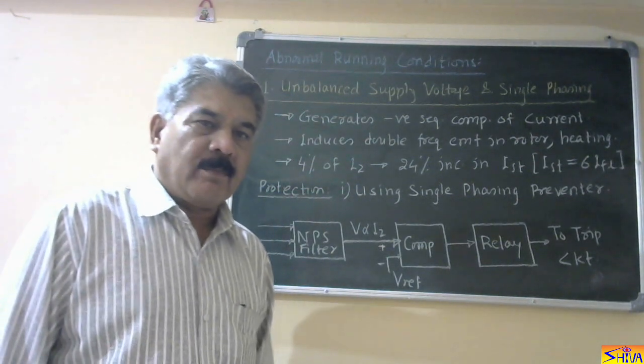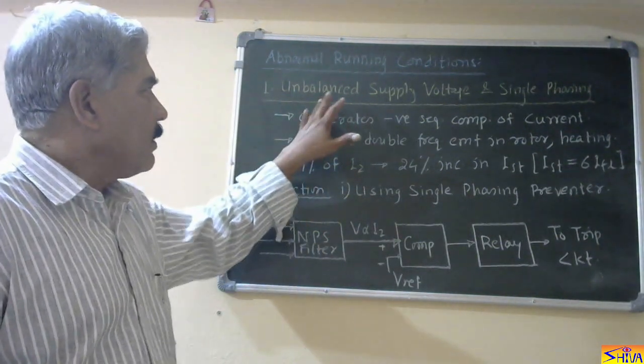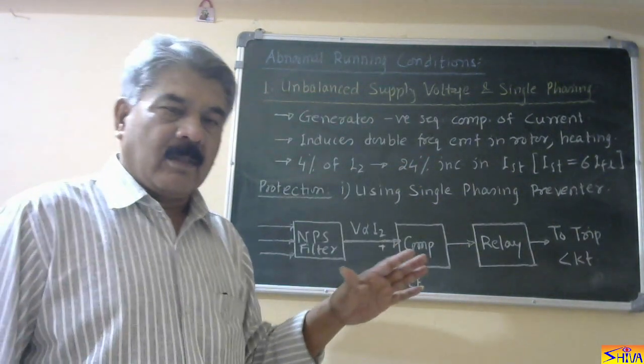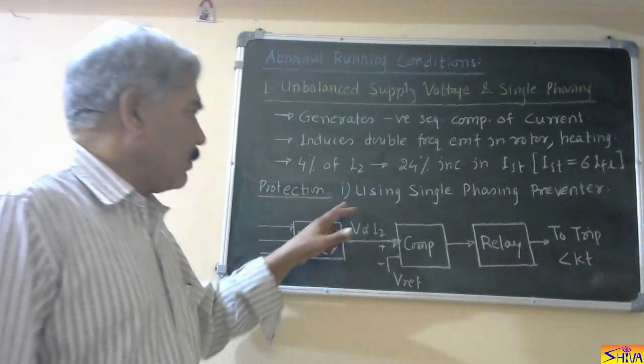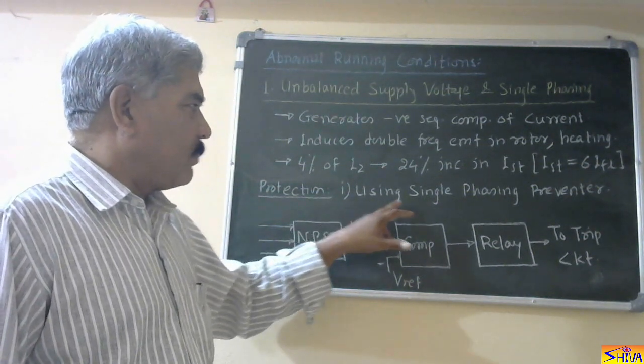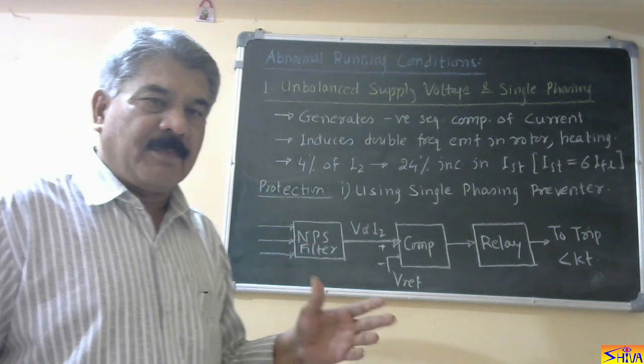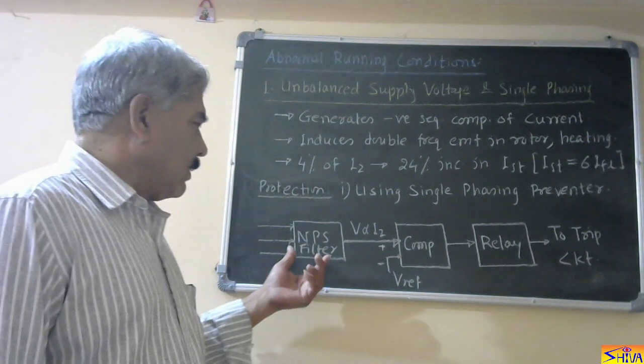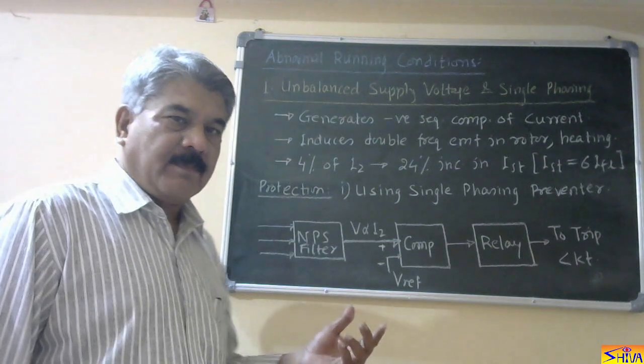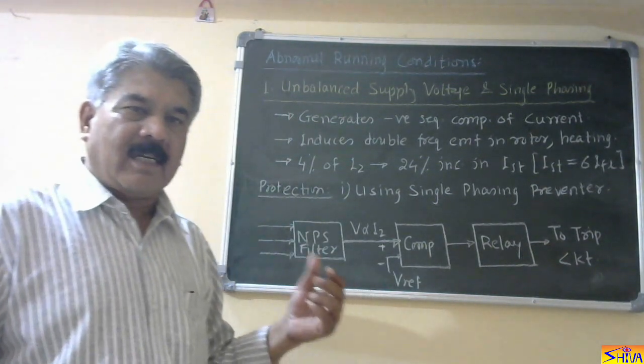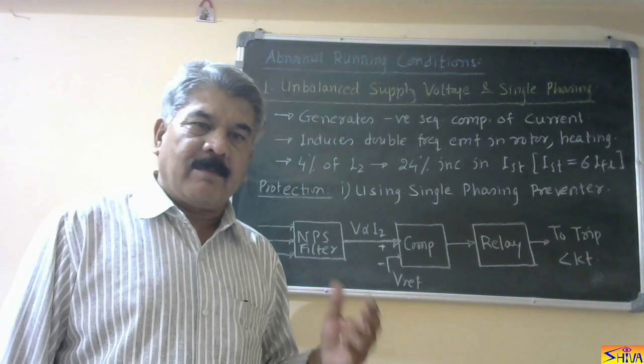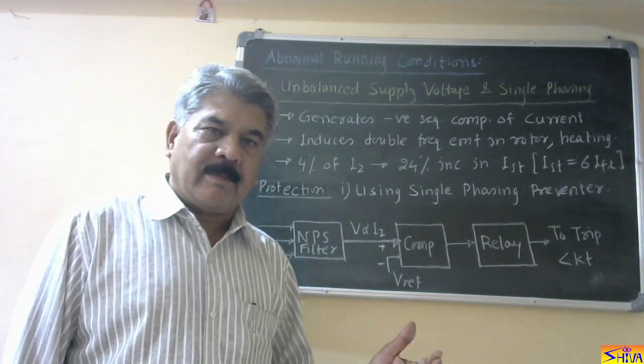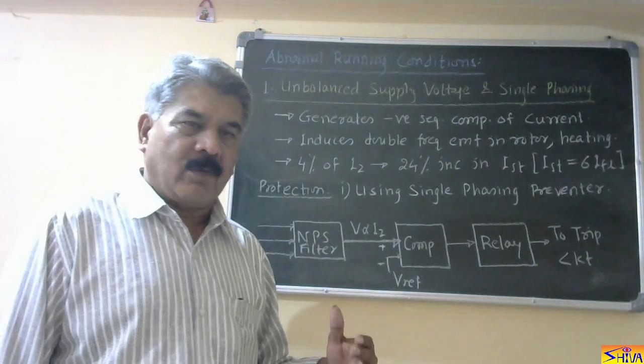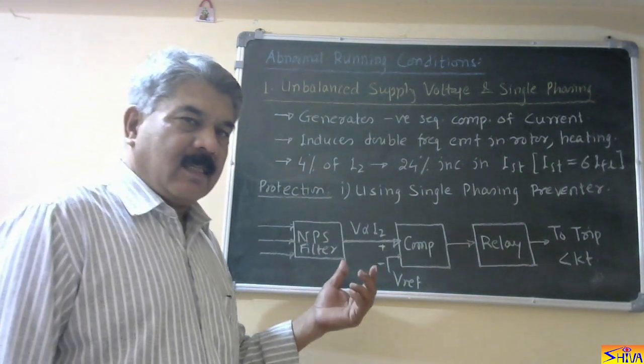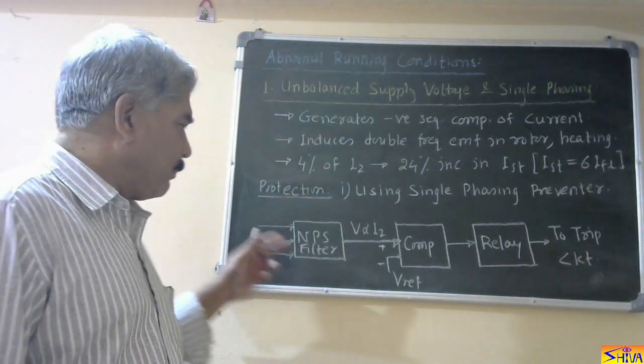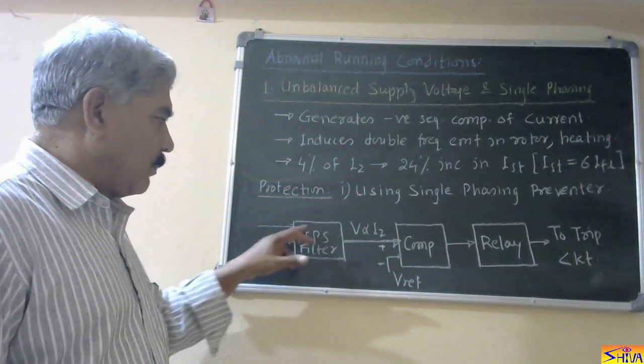Now let us come to the protection scheme. These are the effects of unbalanced supply voltage and single phasing. Now come to the protection side. First, protection is provided by using a single phasing preventer. A single phasing preventer is nothing but the negative phase sequence filter. This protection is the same as that used for generator protection for unbalanced loading. In case of a generator it is unbalanced loading, in case of a motor it is unbalanced supply voltage.